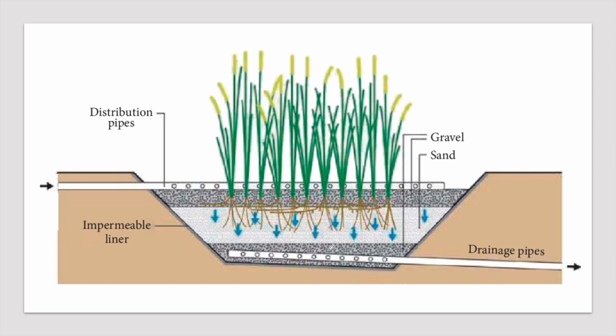The components of a vertical flow constructed wetland are very simple. It consists of an excavated basin filled with media, usually sand and gravel — a bottom layer of gravel, then sand, then a top layer of gravel. We also have reeds, plants that help in the treatment of the wastewater, and of course the distribution pipes and the drainage pipes. The wastewater is pumped into this basin through the distribution pipes and flows vertically — this is why we call it a vertical flow constructed wetland.